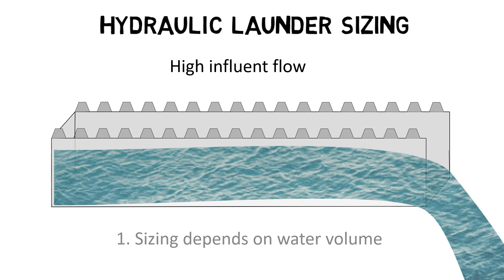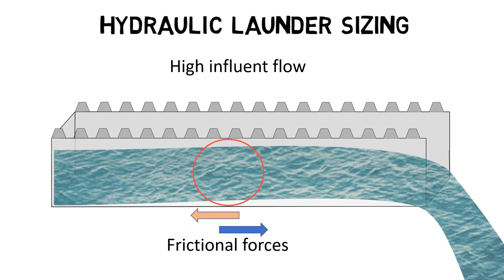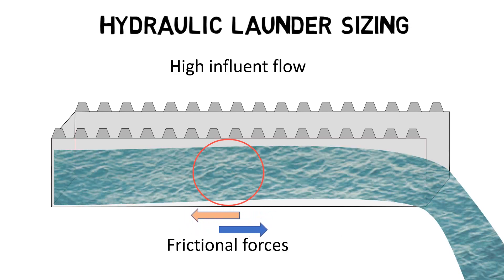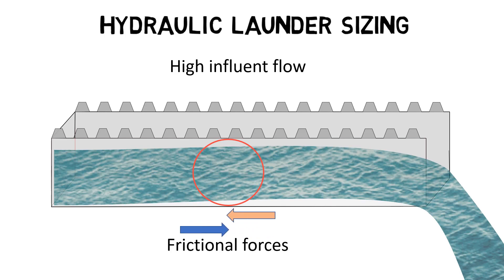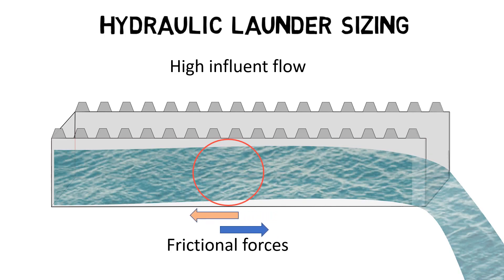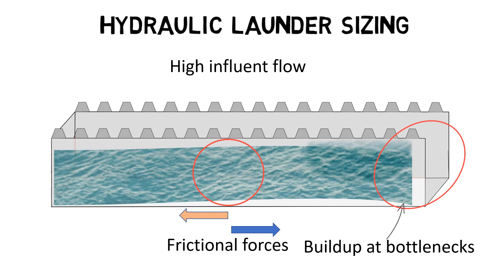Friction forces between effluent water and the launder surface, as well as bottlenecks at the effluent discharge openings, cause buildup of water in the effluent launders. The longer the launders are, the more backwater buildup can be observed.